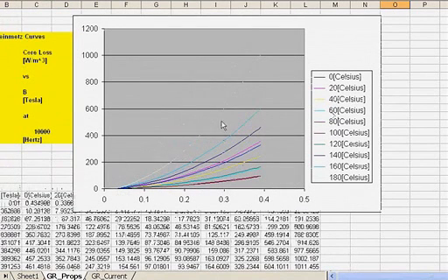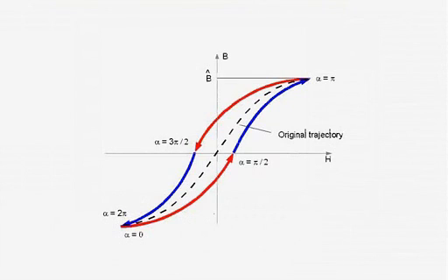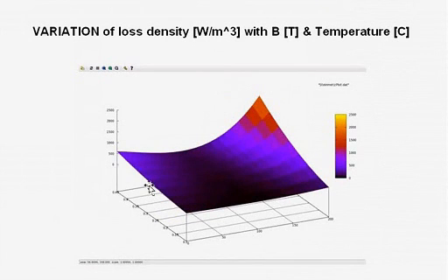It was interesting that with a power ferrite, the designers or the manufacturers minimize the losses at a certain elevated temperature, and maybe I can show that more clearly by this graph. This is a 3D graph of the core loss varying with B and with temperature. The B is the flux density. I have temperature across here on the front axis and peak flux density on this axis here.